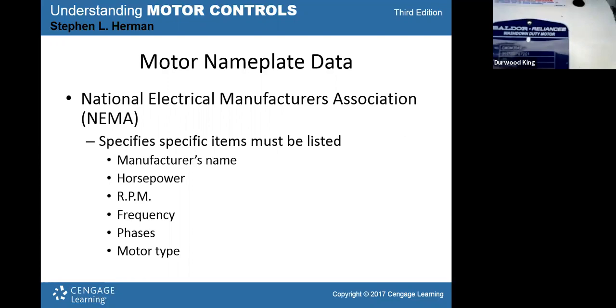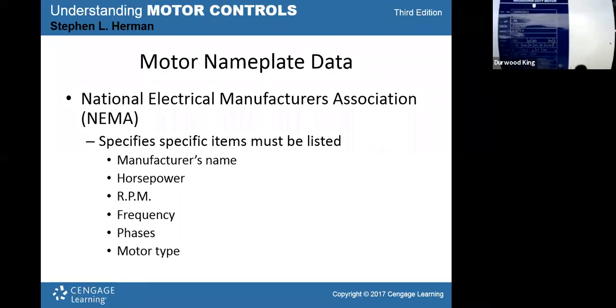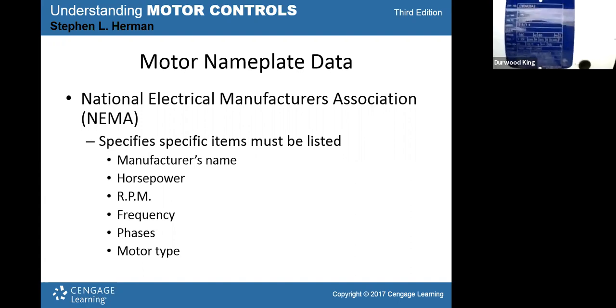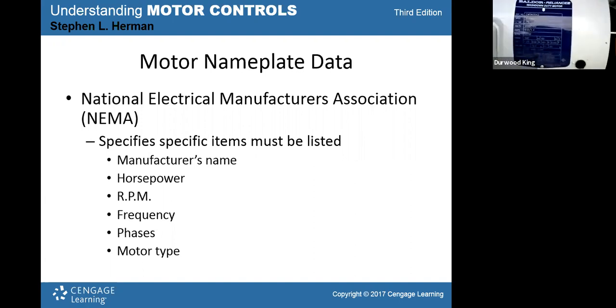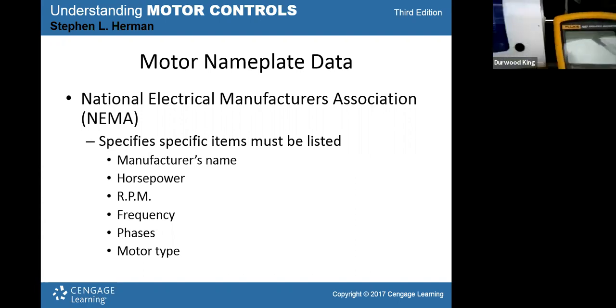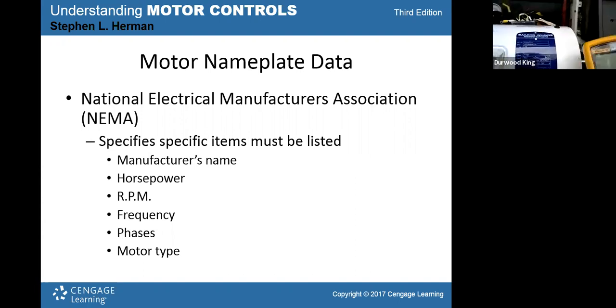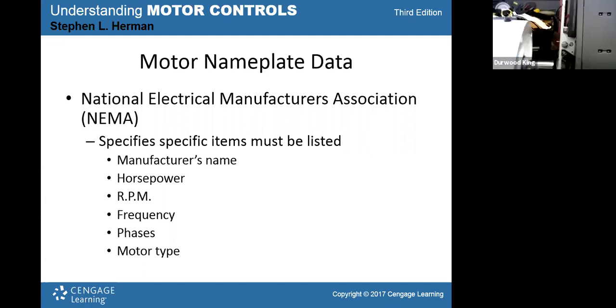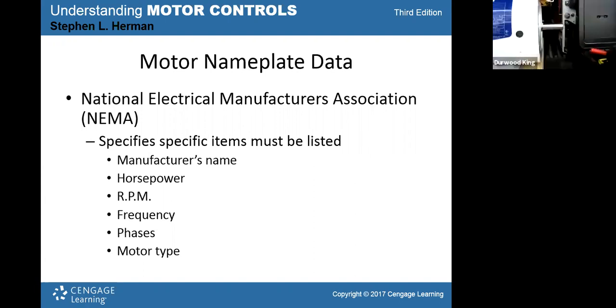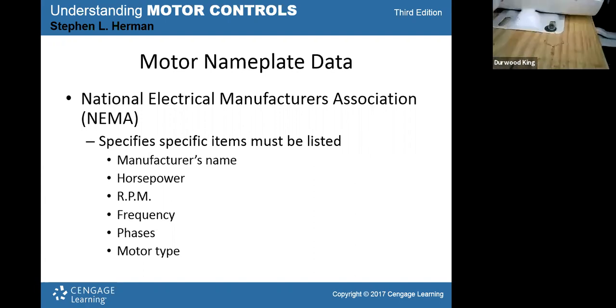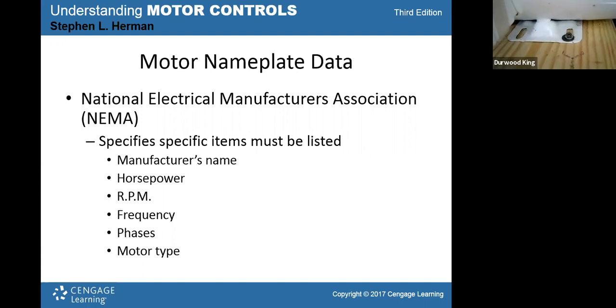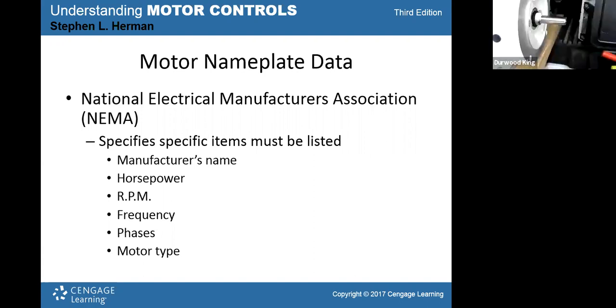If you couldn't get a Baldor, if you had to go with a Leeson or some other brand, then if you have enough information off of that nameplate, you could actually get a motor of some other brand that would bolt right on and do the same exact job, with the same shaft size, the same height from the base to the shaft, the same mounting, like the mounting down here, the foot mount or face mount, however it's mounting.